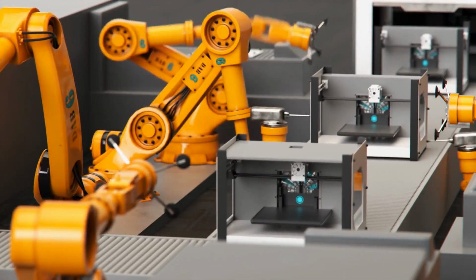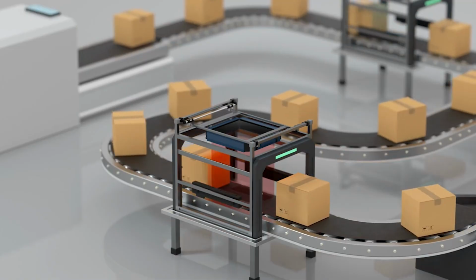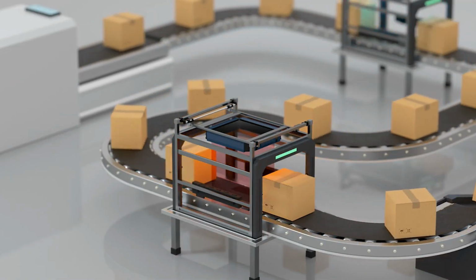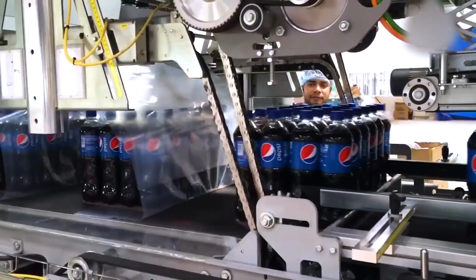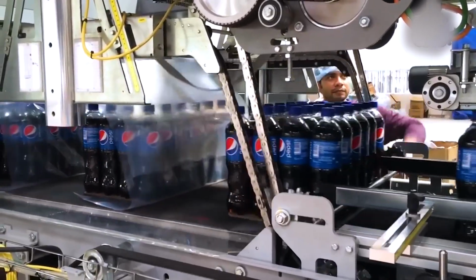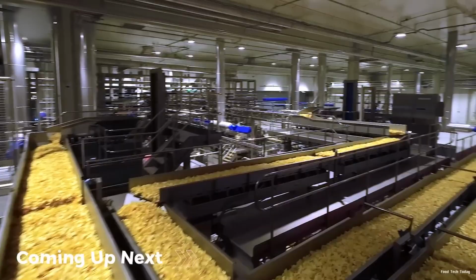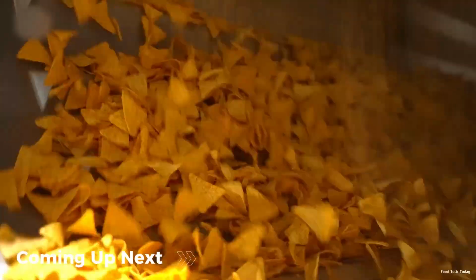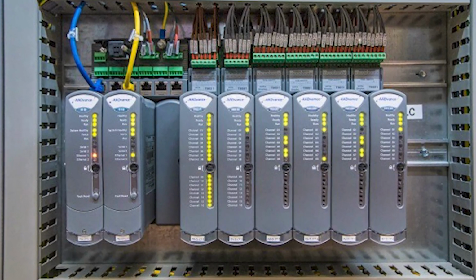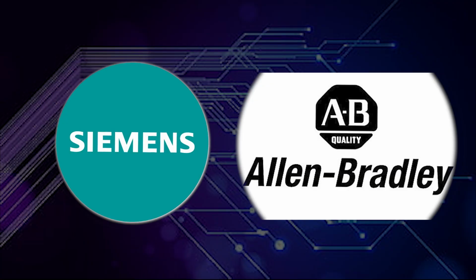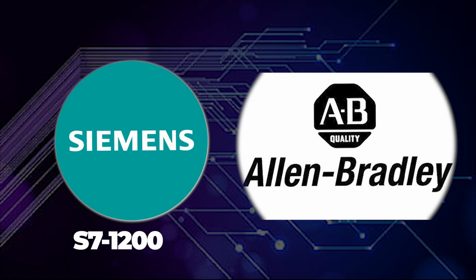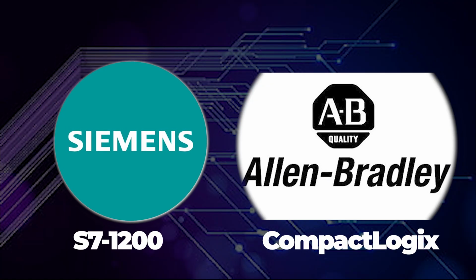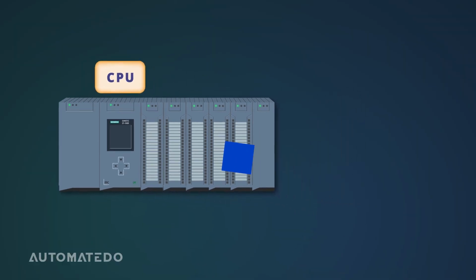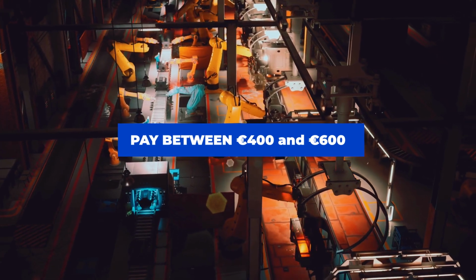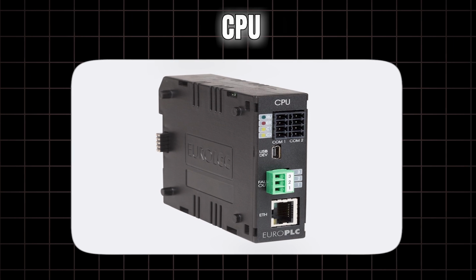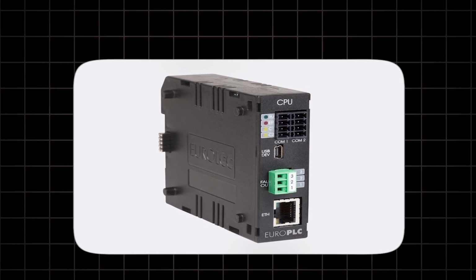Let's say you're automating something simple, like a labeling station on a packaging line. Nothing too advanced, just detecting a product, printing a label, and placing it correctly. Seems easy, right? Here's how the costs play out in reality. You'll likely start with a mid-range PLC, something like a Siemens S7-1200 or an Allen Bradley CompactLogix. Expect to pay anywhere between €400 and €600 for just the CPU, depending on your I/O count and communication needs.